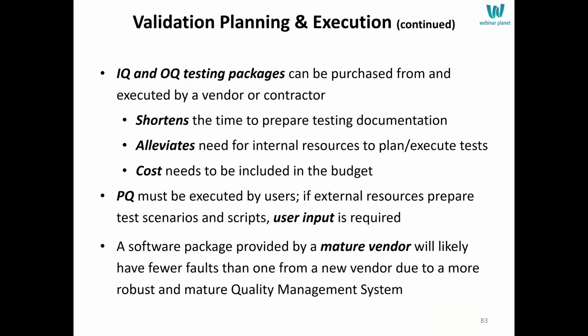Now you can purchase an IQ, OQ test package from many vendors. They sell these. They'll also sell you the service to actually execute IQ and OQ. And this is perfectly acceptable. However, you must make sure you audit the vendor or the contractor, you vet them, make sure that they are capable of doing this work properly. And then you still have to have oversight to everything they do.